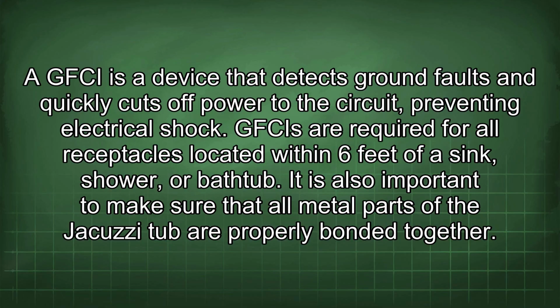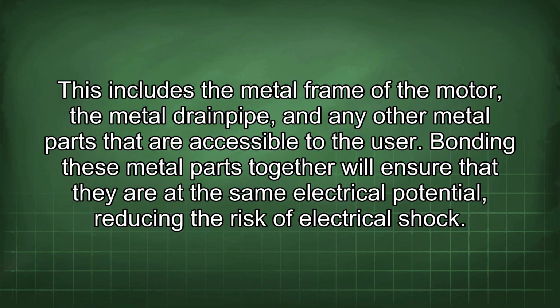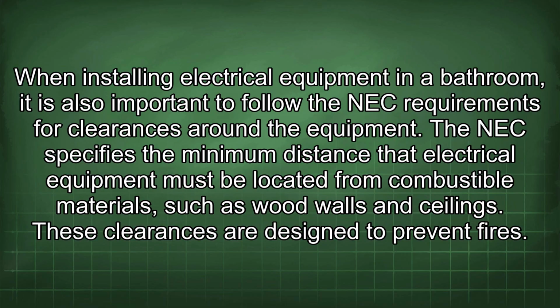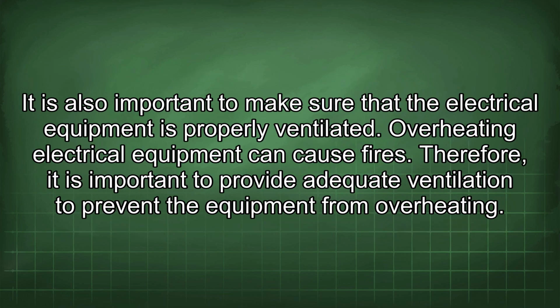It is also important to make sure that all metal parts of the jacuzzi tub are properly bonded together. This includes the metal frame of the motor, the metal drain pipe, and any other metal parts that are accessible to the user. Bonding these metal parts together will ensure that they are at the same electrical potential, reducing the risk of electrical shock. When installing electrical equipment in a bathroom, it is also important to follow the NEC requirements for clearances around the equipment. The NEC specifies the minimum distance that electrical equipment must be located from combustible materials, such as wood walls and ceilings. These clearances are designed to prevent fires. It is also important to make sure that the electrical equipment is properly ventilated. Overheating electrical equipment can cause fires.